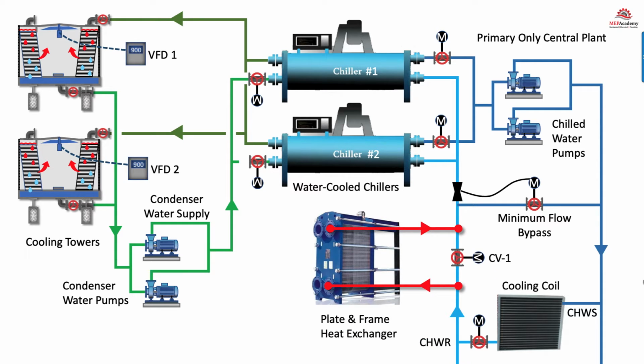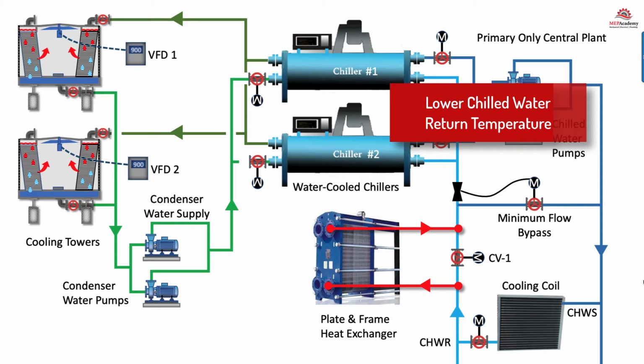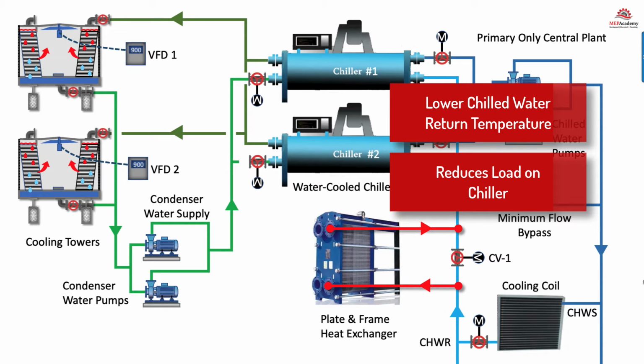To do this, we'll need to add a control valve, CV1, to divert the flow and force the chilled water return to go through the heat exchanger. The waterside economizer can lower the chilled water return temperature before it arrives back at the chiller for mechanical cooling. This reduces the load on the chiller in an integrated system.